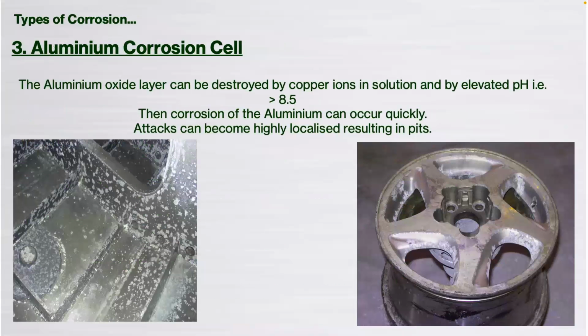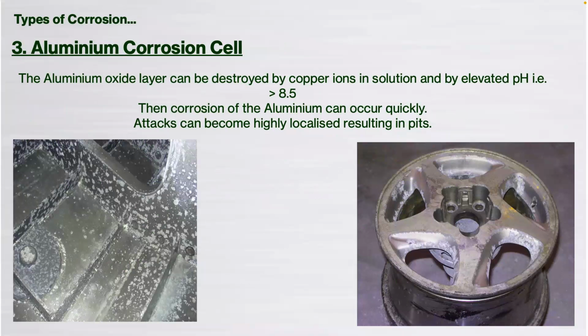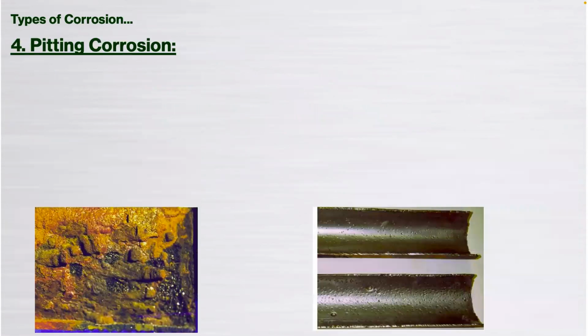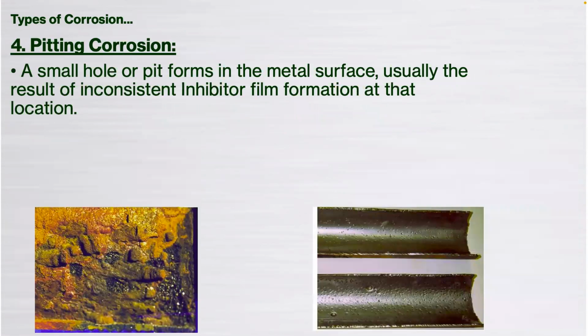Aluminum corrosion cell, really, as I say, aluminum is affected by pH. If you start getting alkaline pH, most commonly when we see aluminum corrosion, it's usually in a closed loop system. It's usually the wrong inhibitor or incompatible inhibitor that's been added to that system, which has caused the problem. A lot of water treatment companies will unfortunately assume, oh, I can use my inhibitor on all my sites that I'm looking after, and they put it into a system that has aluminum heat exchangers or any kind of materials. And the higher pH or alkaline inhibitors run at about 9 to 10. So, of course, we can start seeing problems. Pitting corrosion. So we have a small hole or a pit that forms in the metal surface itself.